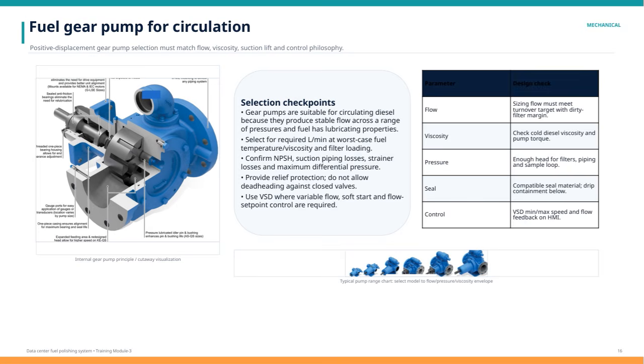When choosing a pump, it's essential to size it for the worst-case scenario, meaning the lowest fuel temperature and highest viscosity you expect to encounter, plus any additional resistance from dirty filters. We have to confirm parameters like the net positive suction head, losses in suction piping and strainers, and ensure the pump can handle the maximum differential pressure. It's also very important to include relief protection so the pump doesn't deadhead against closed valves, which can cause damage. If the system requires variable flow or soft start capabilities, using a variable speed drive is beneficial.